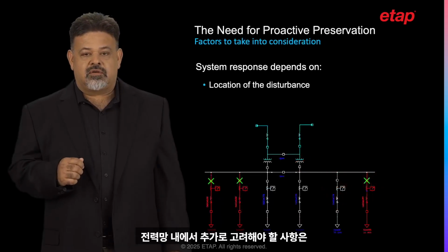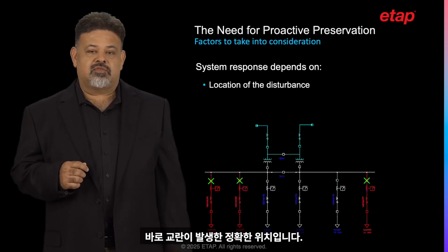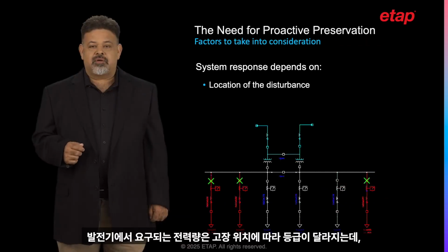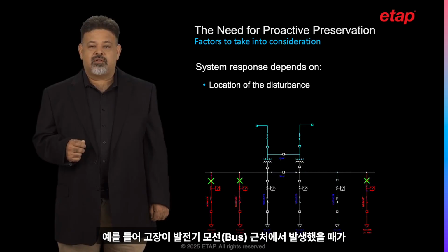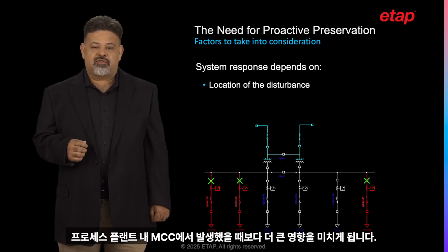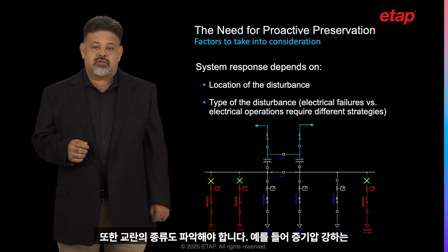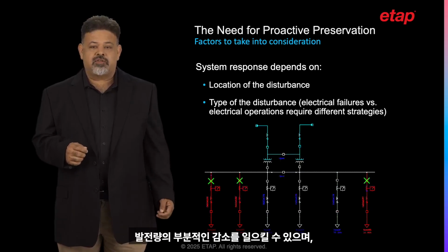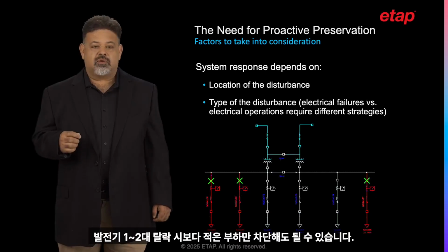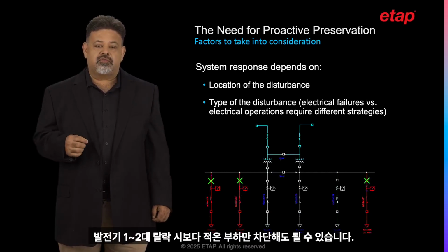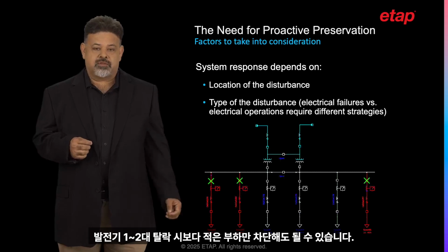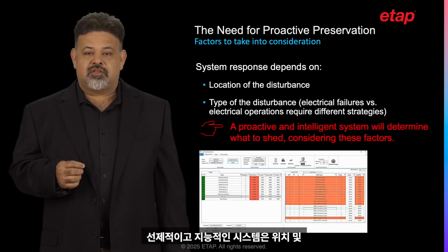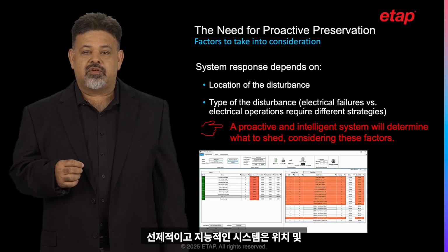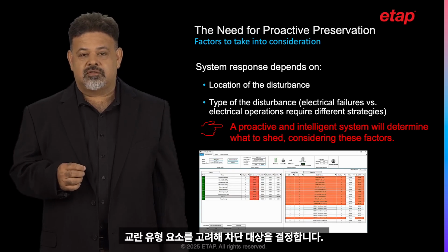Another factor to take into consideration is the location of the disturbance in the electrical network. The power requirements from the generators will be greater when a fault, for example, is closer to the generation bus than when it is far away in an MCC in the process plant. In addition, the disturbance type needs to be understood. A steam pressure drop, for example, may cause a partial decrease of generation, and you may need to shed only a small amount of load in comparison to one generator or two generators tripping. A proactive and intelligent system will determine what to shed considering locational and disturbance type factors.